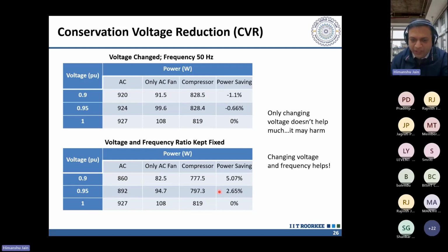Now the question is, how do you change the frequency, since frequency is set by the grid? That's where the inverter comes into play. Inverters come with a digital signal processing chip where I can decide what code to put in, making changes so that when I send a signal to do CVR, it not only changes the supply output voltage but also its frequency. Through that process, we can still get the benefits of CVR. Each AC could respond differently, with different amounts of power reduction, but there's a possibility of doing this without changing anything on the grid side of things.